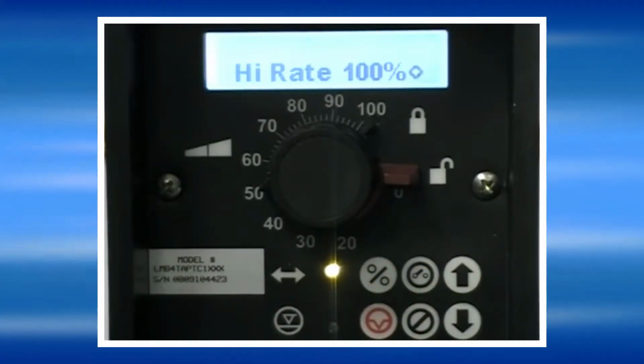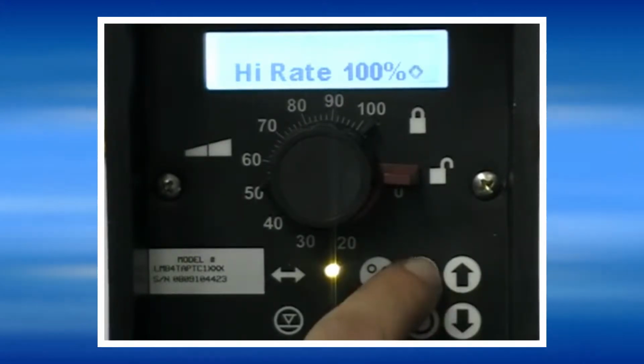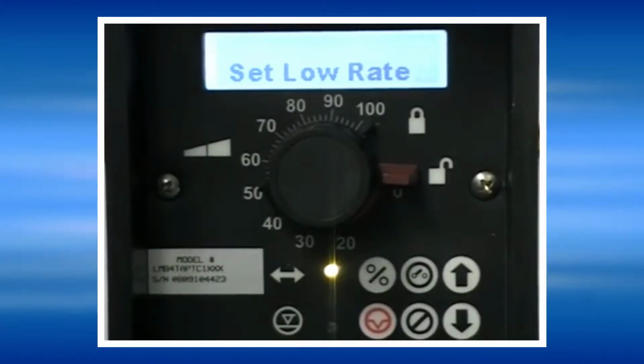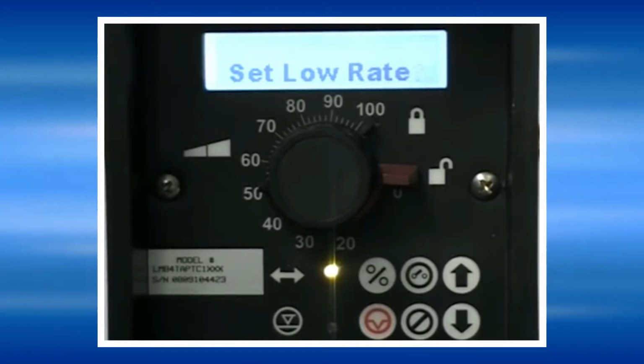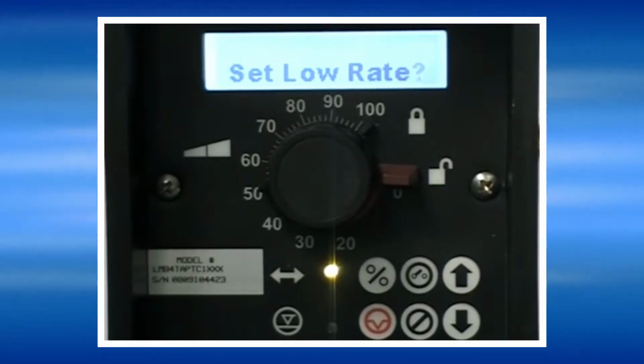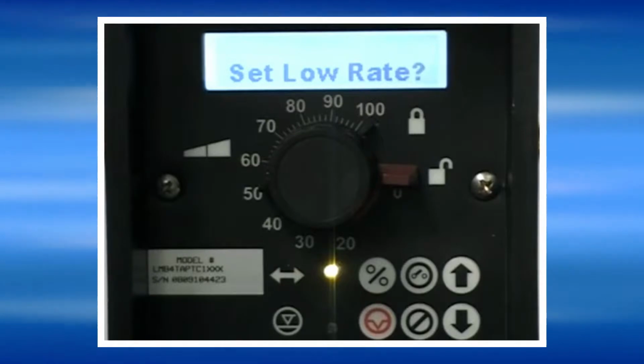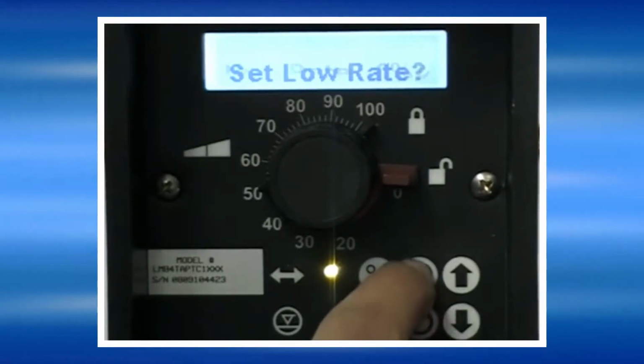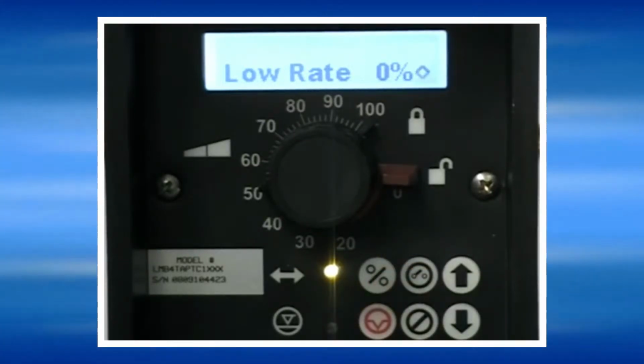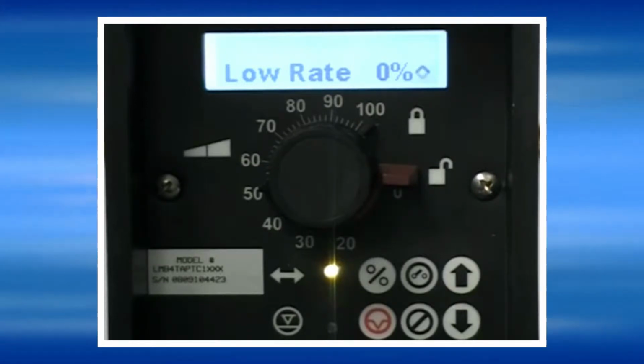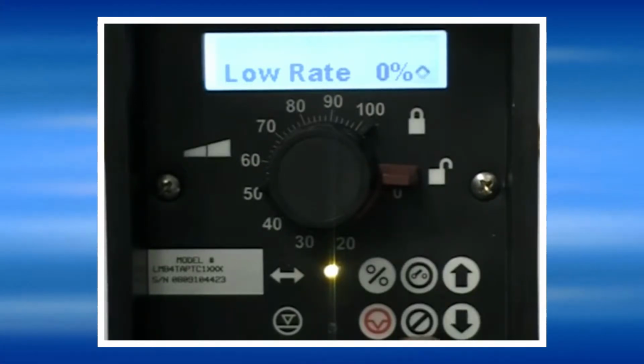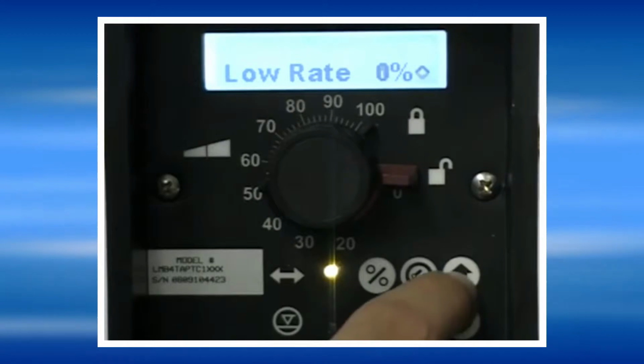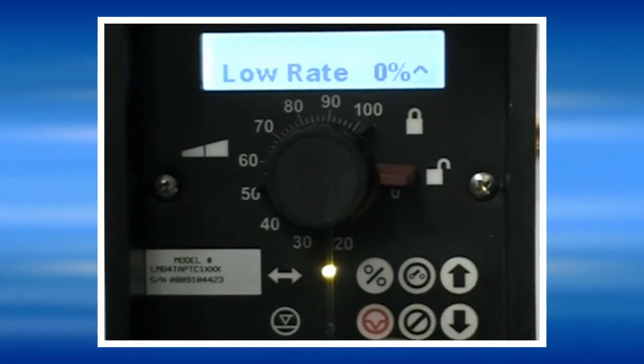This means that the pump will run at 100% speed for the high signal setting. The low rate setting sets the pump speed that you want the pump to run for whenever it receives the low signal setting, which we are going to program here in a moment. This means that whenever the pump receives the low signal setting, it's going to run at 0% speed. You can change this with the up and down arrows on the side if you like.